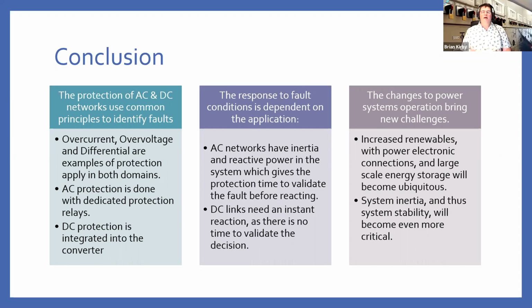And how you respond to the fault on an AC system is different to how you respond on a DC system. AC networks have inertia and they have reactive power, and that gives them time to actually validate what's going on before they take actions. DC networks don't have that luxury, so they just have to react instantly to what's going on. Increasingly, renewables and power electronics are becoming ubiquitous.